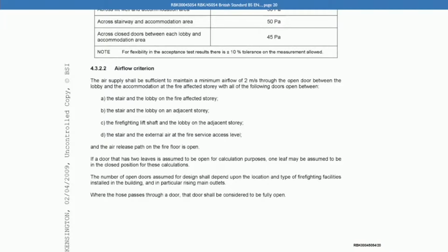Part of that you're reading there is from a pressurised system. Well, this is for a Class B pressure differential system, and we understand the airflow rate of 2 metres per second to come from this part of this British standard. When he gave evidence last week to the inquiry, Mr. Hanson, the building control officer, said that his expectation was that PSB would be testing as part of the commissioning process with other doors open or closed in accordance with this British standard. He said the technical submittal proposed the 2 metres a second airflow test in accordance with this standard. So my expectation is that it would be tested in accordance with this test procedure, opening and closing the relevant doors to the Class B system. So that's clearly stated in the technical submittal.